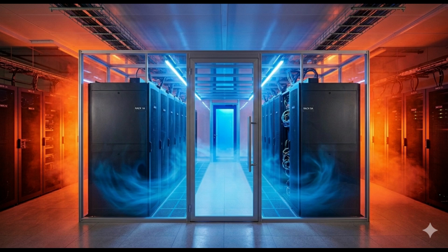And then the air passes through the servers, picks up the heat, and exhausts into the hot aisle. The hot aisle is strictly an energy collection zone. The thermal equation there is that the total heat removed has to perfectly equal the sum of the heat generated by every single rack. It is not a comfort zone for humans. It is purely a transport plenum for waste heat.